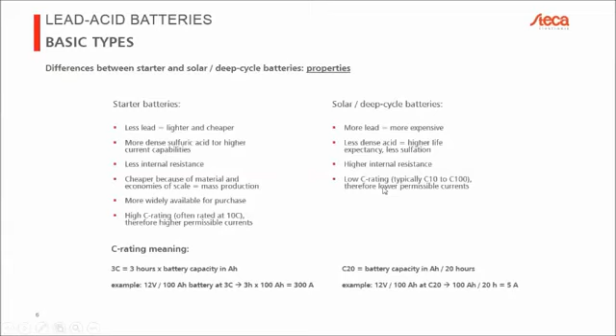For solar deep cycle batteries, remember we had more lead, which means they're more expensive. We have less dense acids, so that means a higher life expectancy, and less sulfation, which you'll see later—not only eats away the lead but also results in crystals. We have a higher internal resistance, which is not something we want; this is the result of having a less dense acid. It means we can extract less current out of the battery, so we have a lower C rating—we can take less current out of the battery.